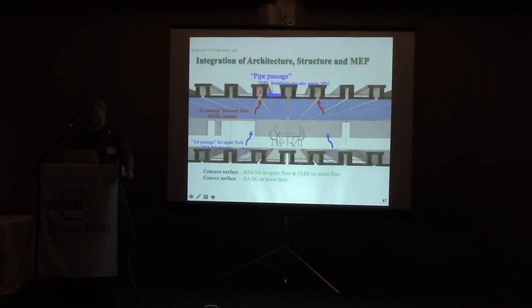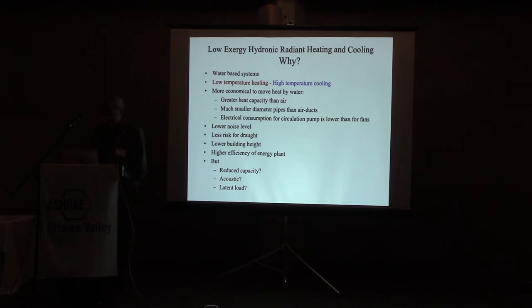Their ceiling looked a little different than we normally see. They had a kind of special concrete ceiling, and they put the piping here. The space in between was used for air, but also for lighting. Right now, I think that will be submitted for an ASHRAE award as well. I hear that they have been very successful, satisfied with both the energy use and the indoor environment. What measurements are being done right now? So it is a system that, even if you are in a humid area, if you design it well, make sure to dehumidify when it's necessary, and have a control that takes that into account, is useful also in more humid areas.